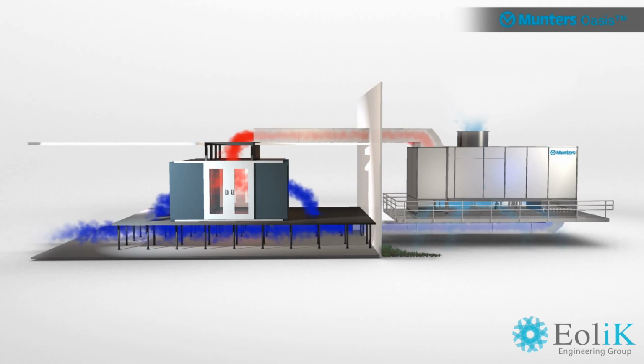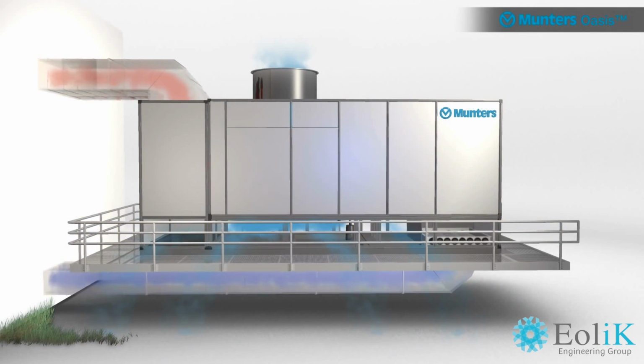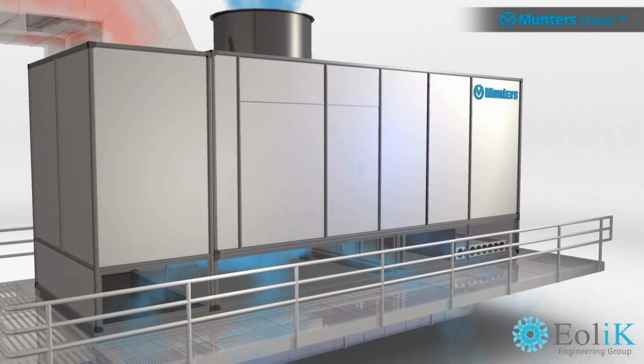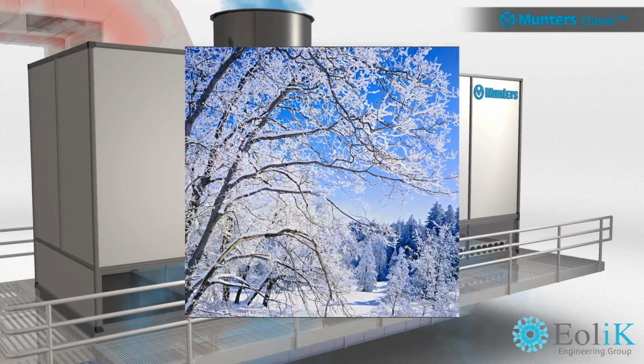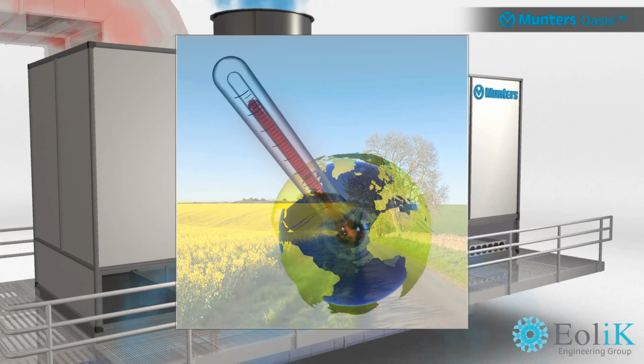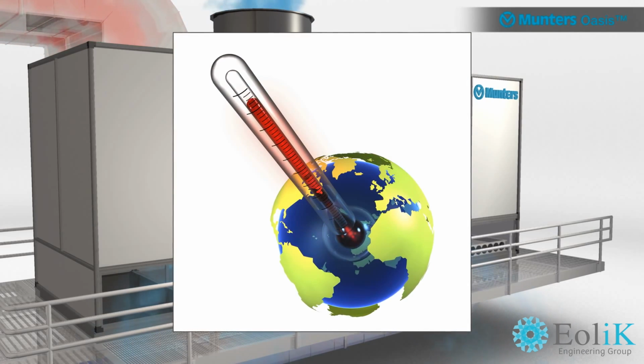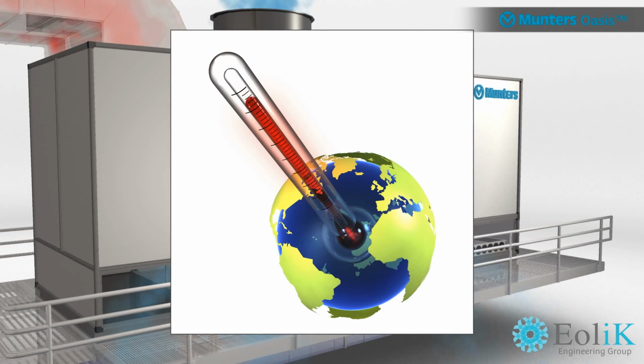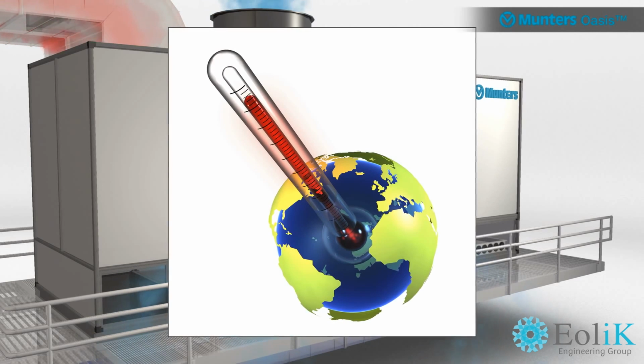Munters, the global leader in energy-efficient air treatment, has developed the most innovative, energy-efficient and cost-effective solution, the Oasis Indirect Evaporative Cooler. Oasis uses evaporation of water as the principal source of energy to provide an indirect, evaporative air cooling solution. Unlike other indirect evaporative cooling systems, Oasis operates dry in winter and in evaporation mode in summer. In really hot and humid outside conditions, the unit then operates in a third mode, with a combination of evaporation and direct expansion DX.